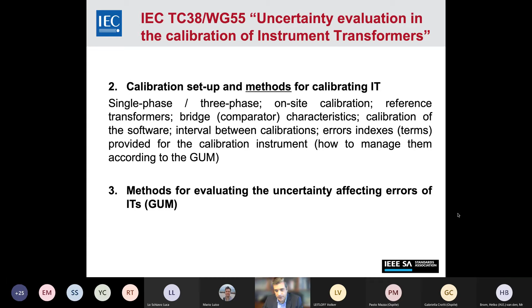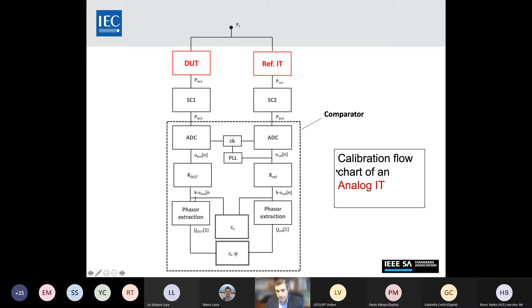In particular, I don't know if, yes, the model is working. Consider the device under test, which is the instrument transformer to be characterized, and the reference IT. This is very typical. Now, the comparator is here. This is typical, used nowadays for, let's say, calibration of instrument transformers. So this is what we have as is.